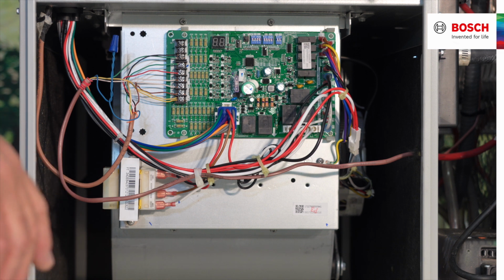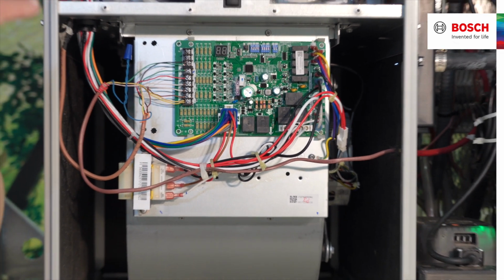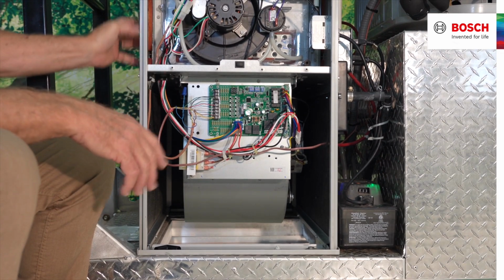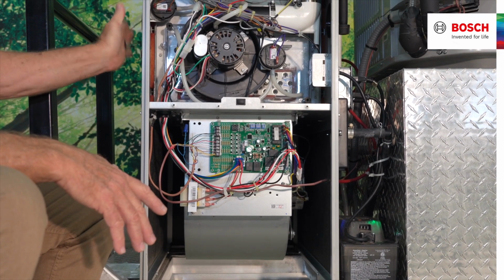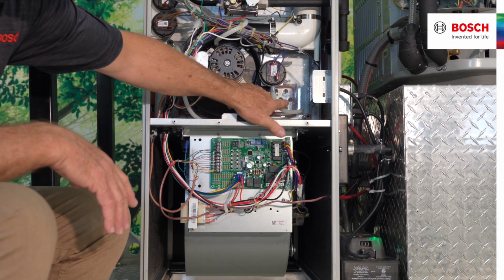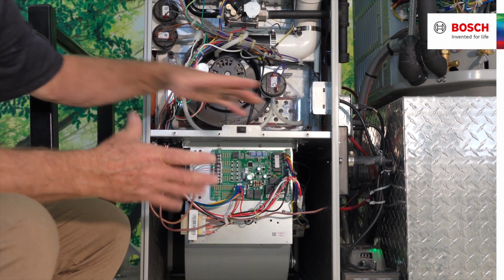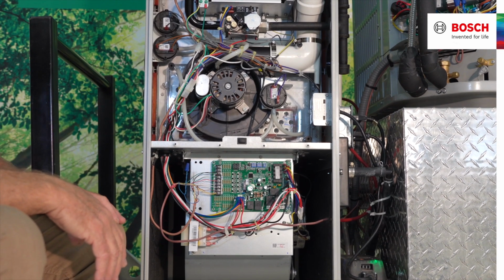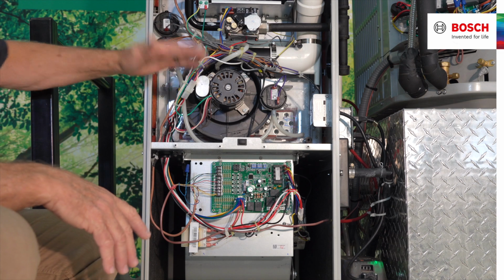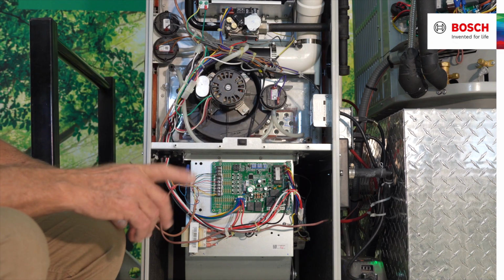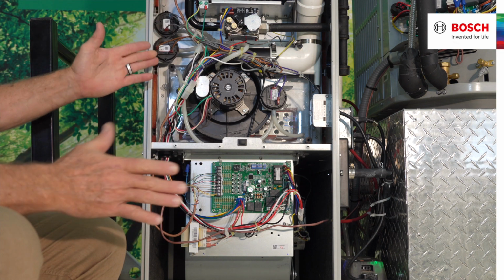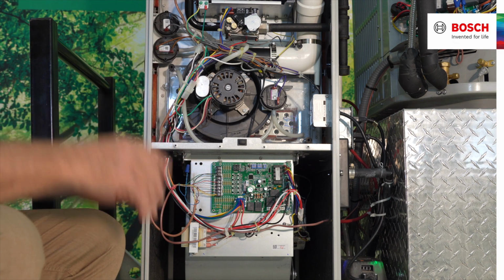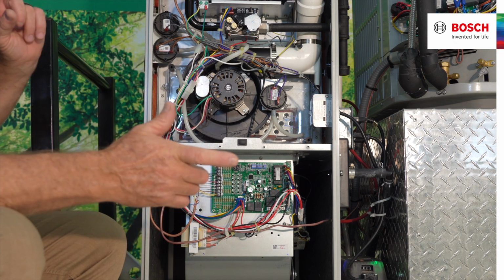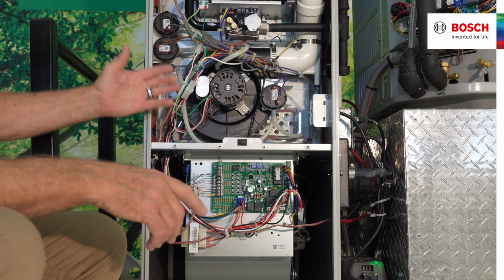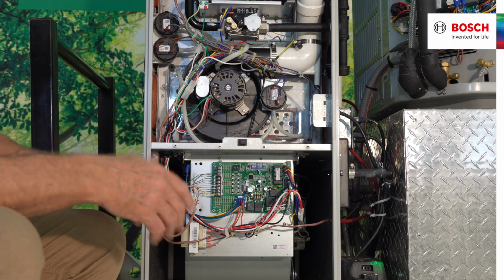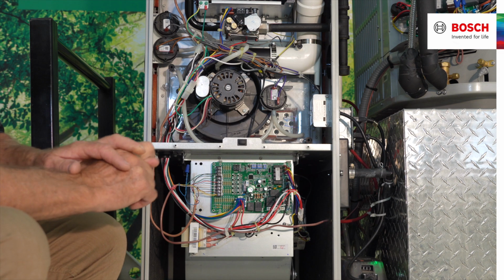Other than that, guys, it is a very, very sturdy piece of equipment. It's very heavy. The metal is very, very thick. And remember that when we're setting this unit, we're going to tilt this unit toward the front. This allows for the secondary heat exchanger, which has a clear plastic cover so I can see what's going on within it. I can see the condensate water coming down and going into the exiting tube. But we tilt that so that it exits and it doesn't back up. If we don't tilt that furnace toward the front, whether in a horizontal situation or in an upflow application like this, we do not get all of those BTUs that this furnace can give us in a W2 call.